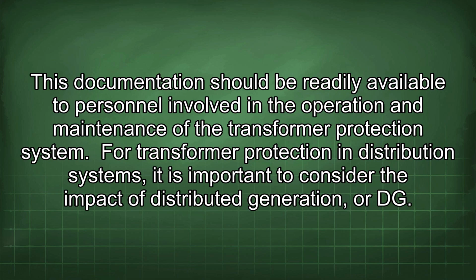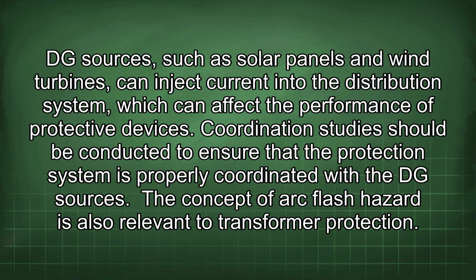For transformer protection in distribution systems, it is important to consider the impact of distributed generation, or DG. DG sources such as solar panels and wind turbines can inject current into the distribution system, which can affect the performance of protective devices. Coordination studies should be conducted to ensure that the protection system is properly coordinated with the DG sources.